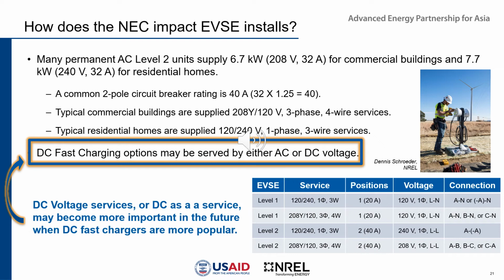However, the power delivered to a vehicle from these devices also depends on the voltage service. Level 2 units may operate at either 240 volts, common in households, resulting in 7.7 kilowatts of power, or at a lower voltage of 208 volts, commonly found at commercial businesses, delivering a slightly lower power of 6.7 kilowatts from a 32 amp device.